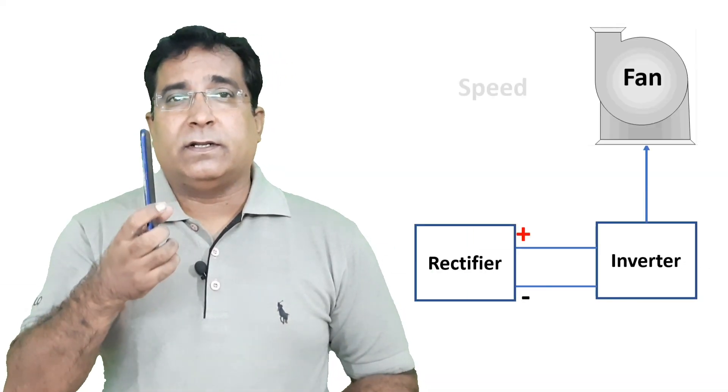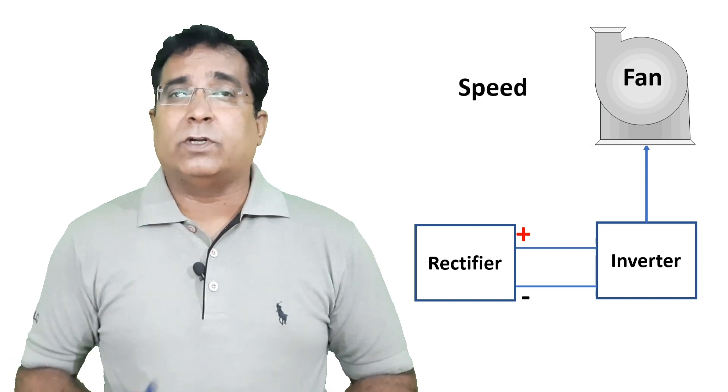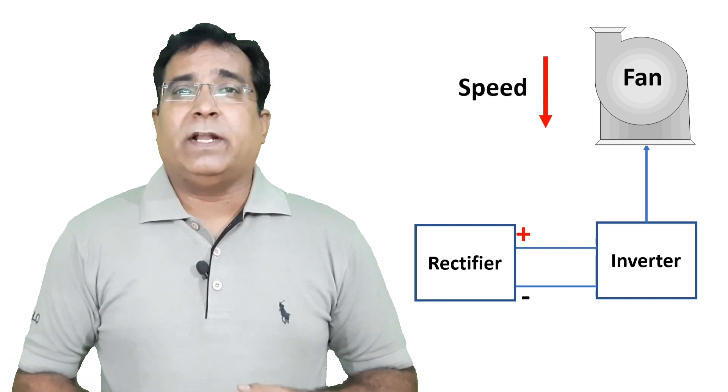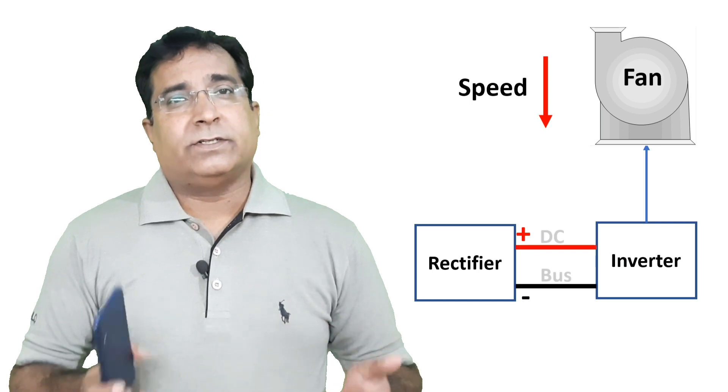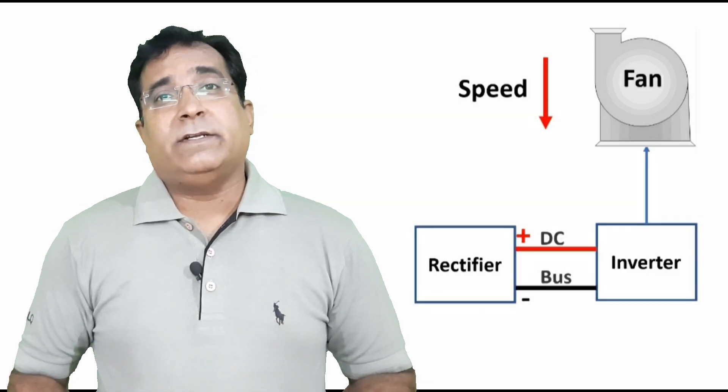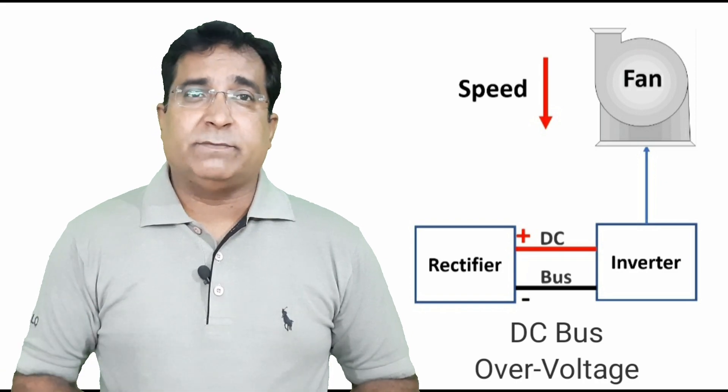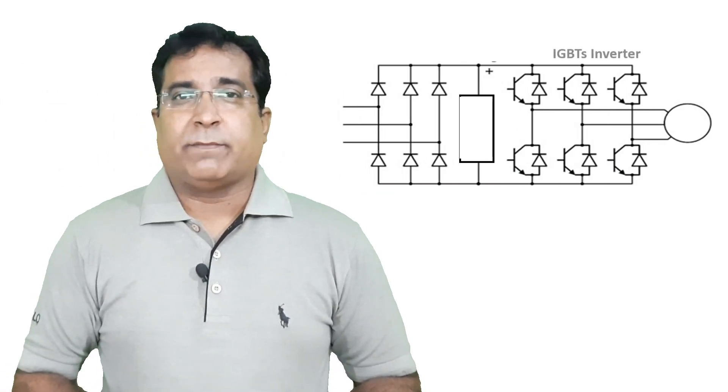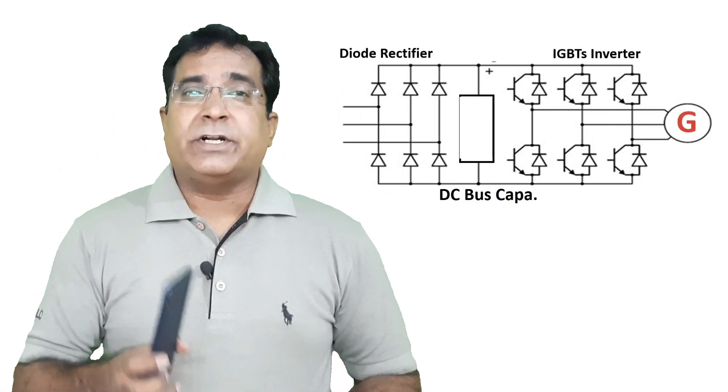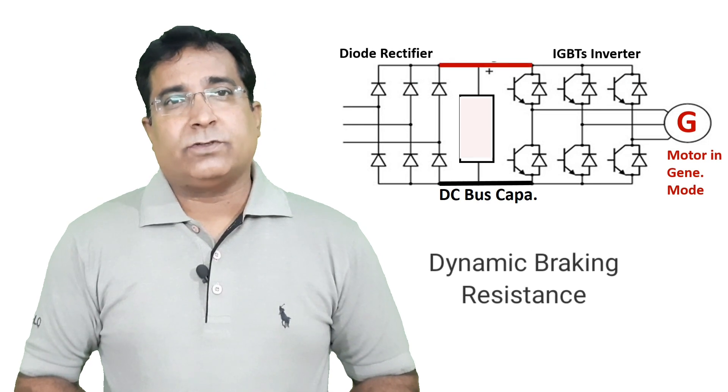For example, a fan application: if a sudden speed set point is changed from higher to lower speed, the inertia of the fan pulls the motor and regeneration takes place which causes the DC capacitor bus voltage to build up and trips the drive with DC bus overvoltage fault. Now to eliminate this problem a resistance is connected which shunts the DC bus capacitor. Resultant regenerated energy is wasted as heat across resistance.